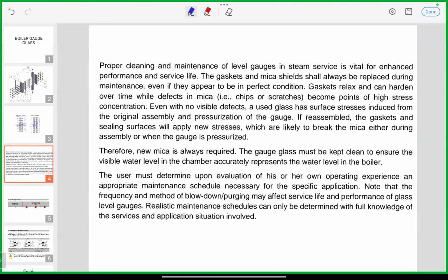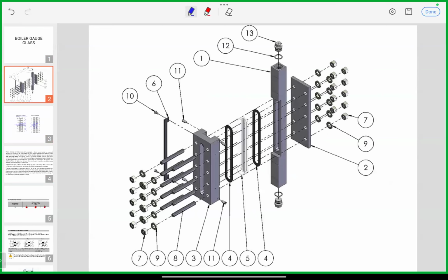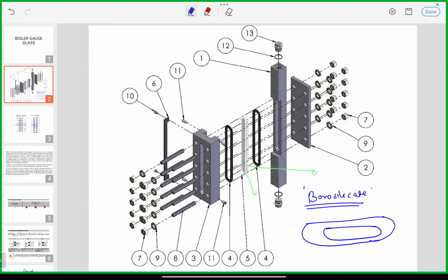Now, when you open or dismantle your gauge glass, an important maintenance point concerns the glass itself. Generally, this glass is made of borosilicate material. So what type of defects can be expected here? There is a possibility of pitting and wire drawing effect.